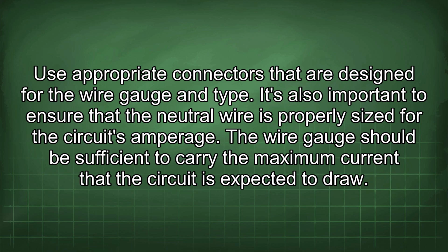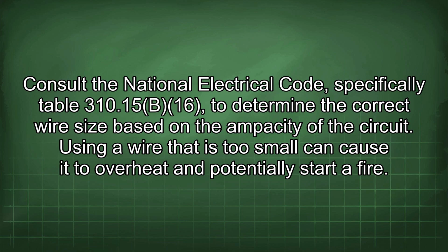It's also important to ensure that the neutral wire is properly sized for the circuit's amperage. The wire gauge should be sufficient to carry the maximum current that the circuit is expected to draw. Consult the National Electrical Code, specifically Table 310.15(B)(16), to determine the correct wire size based on the ampacity of the circuit. Using a wire that is too small can cause it to overheat and potentially start a fire.